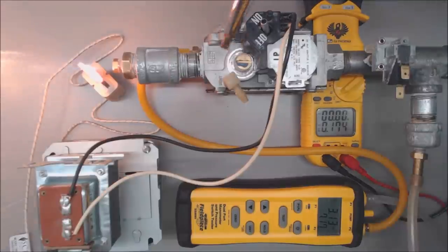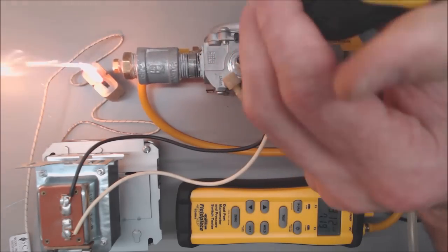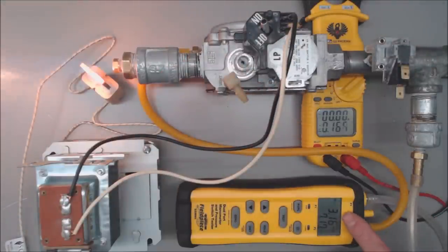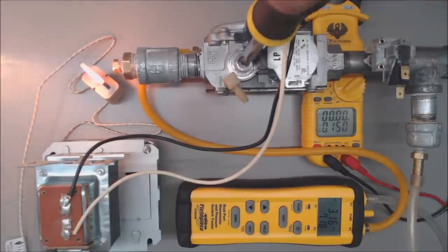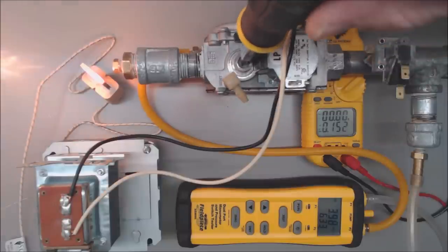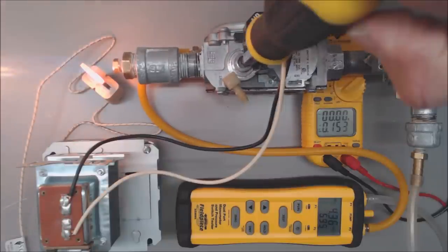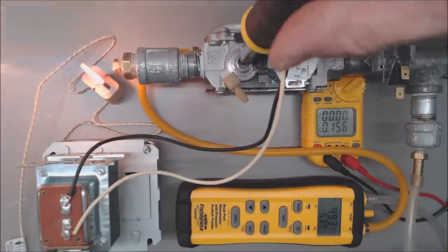So let's go ahead and adjust this. Okay so you see that we're reading 3.17 presently, and if we were to turn this clockwise we're going to go up to a higher gas pressure. So right there we have 3.98.